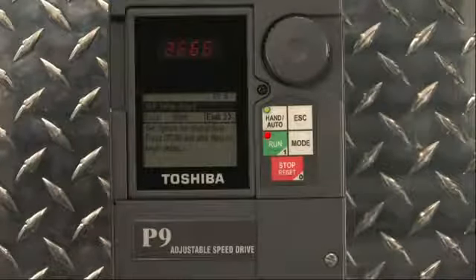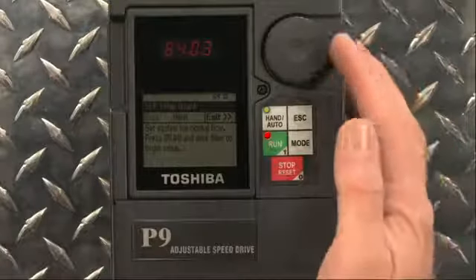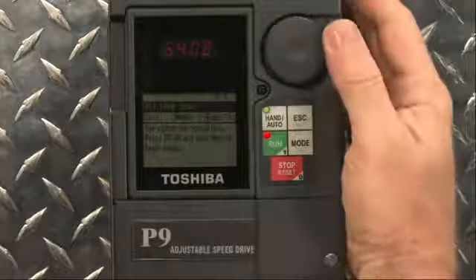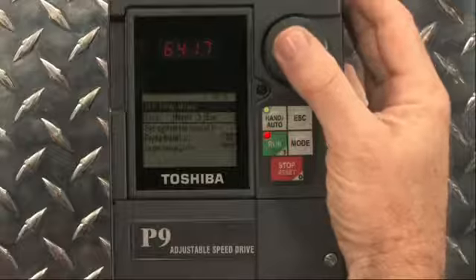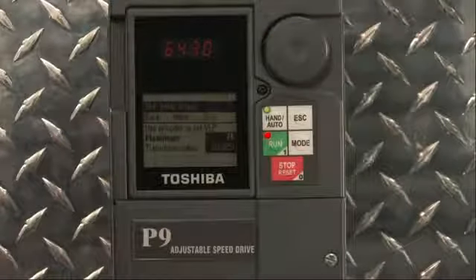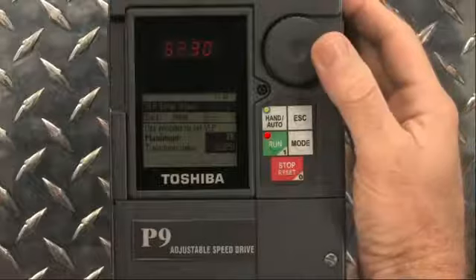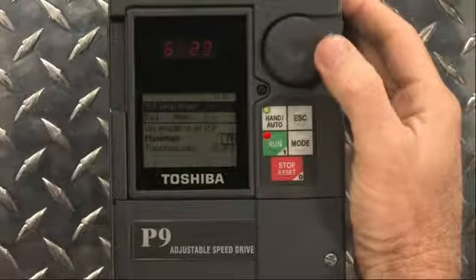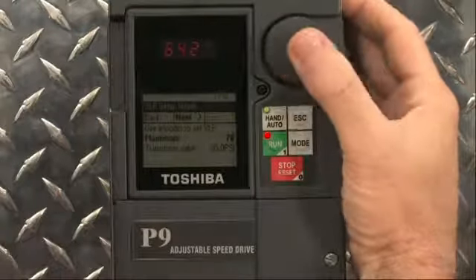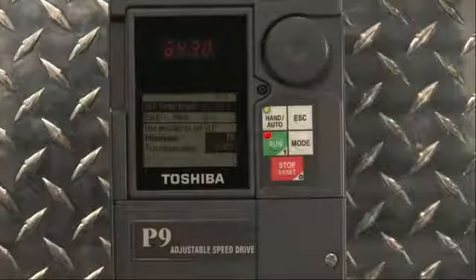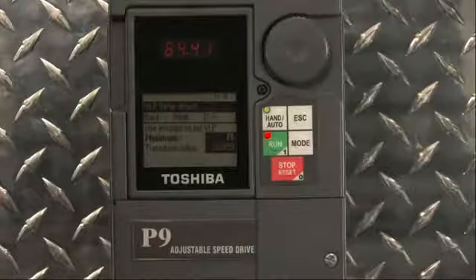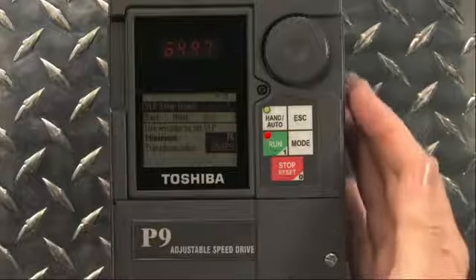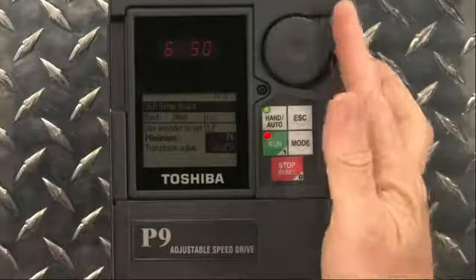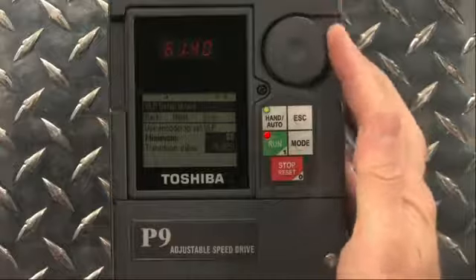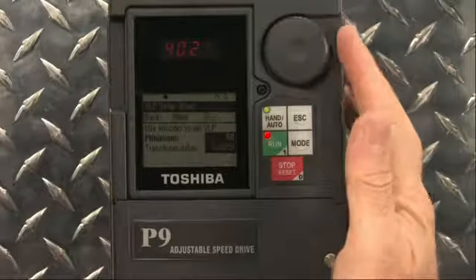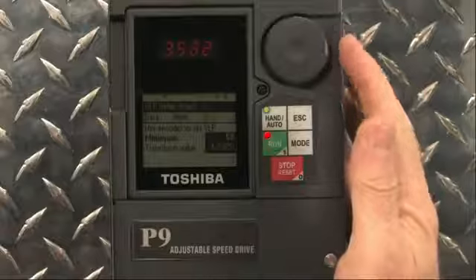The screen displays the pump VLP maximum and to the right a number. This number corresponds to the pump's maximum flow and indicates the upper end of the operating band. Be sure to make note of this value. VLP maximum will not normally need to be adjusted, so let's scroll to Next and press Enter. Now the screen prompts us to set VLP minimum number. In order to modify this parameter, scroll to the number and press Enter to select it. Notice how the number becomes highlighted. By rotating the encoder counterclockwise, the number will begin to decrease and the pump will begin to slow down.